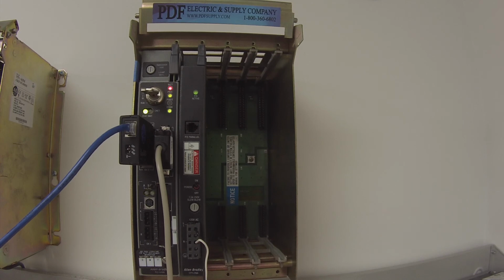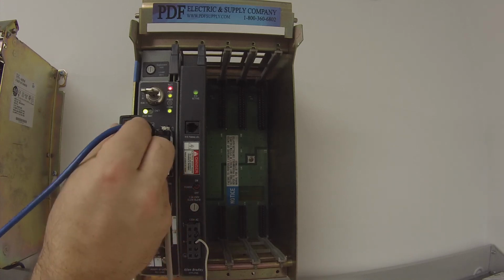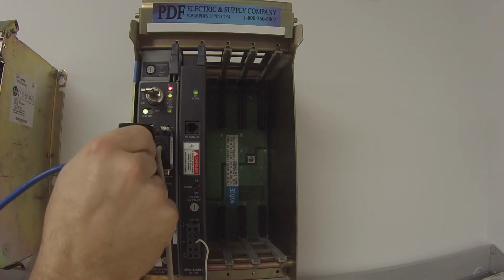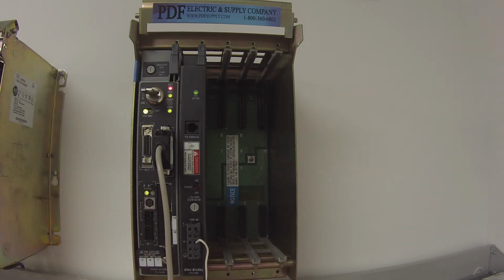And the other thing that I usually do is, just to make sure I'm not pinging another device and getting a false sense of security, I'll unplug this Ethernet and or the transceiver, and I'm going to go ahead and ping it again. So if I've gotten a successful ping and it replied, then the second time around without it, I shouldn't get a reply. What I'm doing here is I'm just testing to make sure that I'm not pinging another device that's been set up on my network that I don't know about. Okay, so now that I do that, and I have no response at all. So that test is good. So that's generally what we do to test these processors if we feel it's troubled.